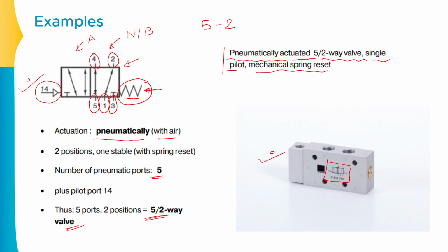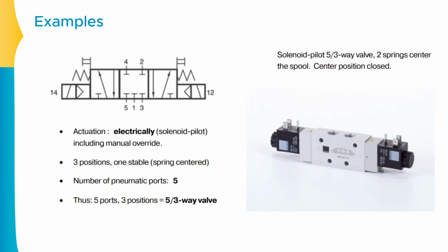So whenever you see such kind of complex terminologies, don't get confused. This basically represents each and everything which is available inside the direction control valve. Clear? Let us see some more complex examples. This is the last example, one of the most complex. As you are observing, this specific valve has a total of 3 positions and 5 ports available. So this is the 5/3 way valve. Okay, understood the basic thing. This is the pressure line, these are the working lines, and these are the return lines.